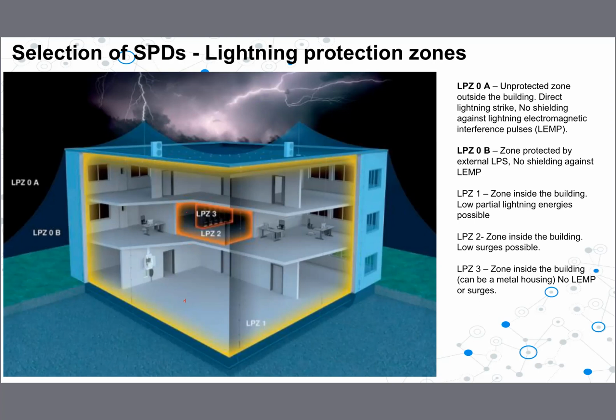An SPD is like an MCB or RCCB. If a surge current passes through which is not handled by the SPD, then definitely it will be damaged. That happens if you select an incorrect SPD. Other than that, the other two factors and physical damages are what we can see at site level.